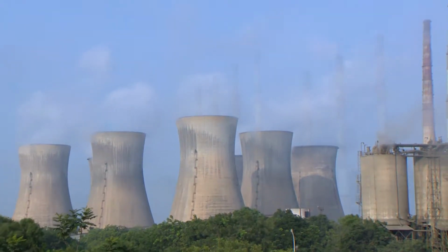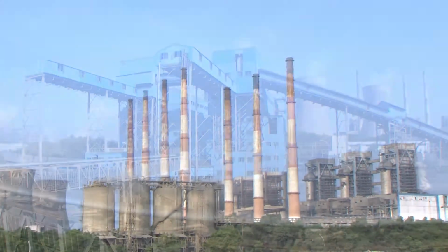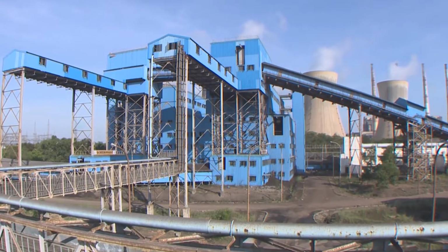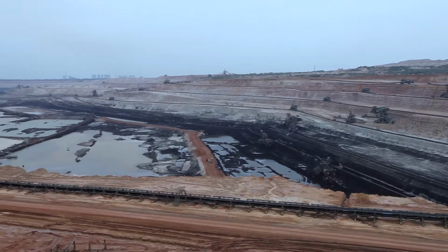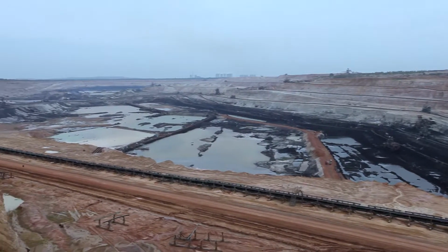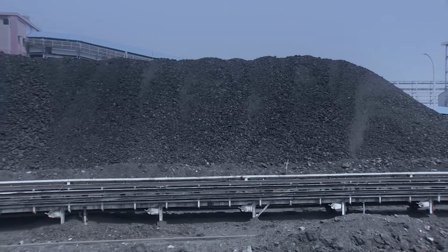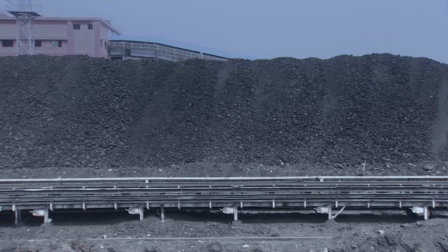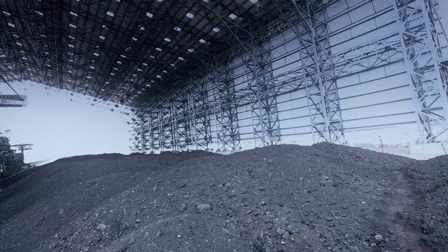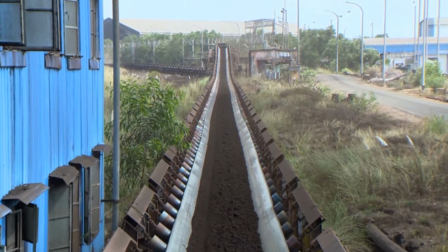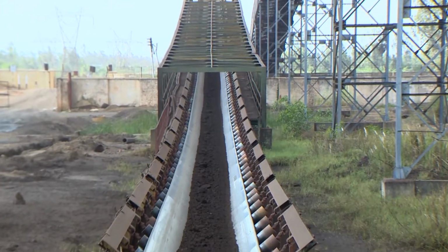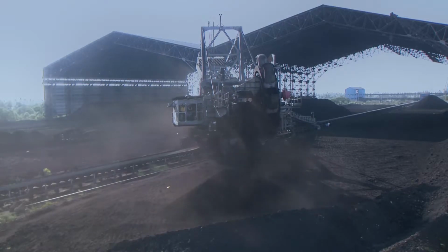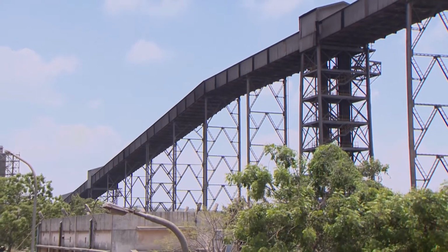Lignite handling system. Neyveli thermal power plants are pit-head power stations, that is, the power plants are located near the mines. The primary fuel for the Neyveli thermal power plants is lignite, which is low-grade coal with a gross calorific value of 2700 kilocalories per kg. The lignite excavated at the mines is transported to the thermal power plant by belt conveyors. Then lignite is stored in the open stockyard or in closed bunkers.